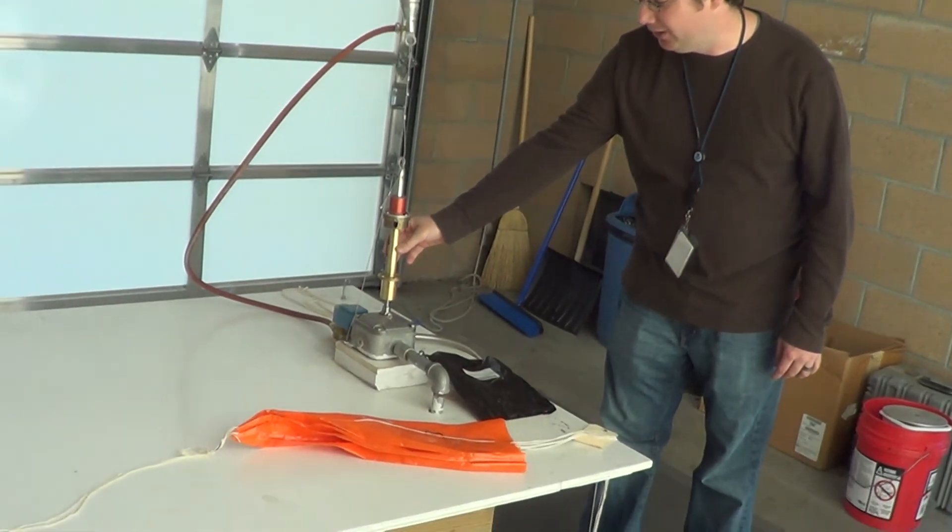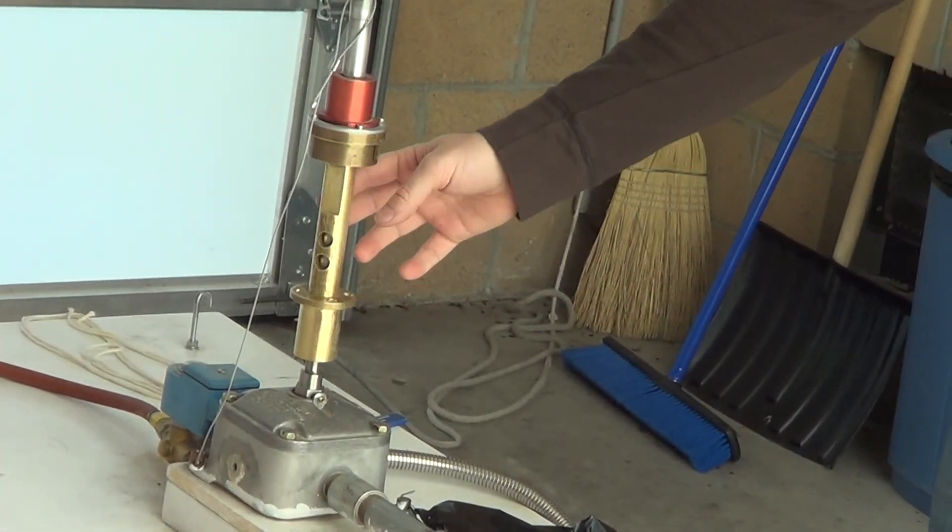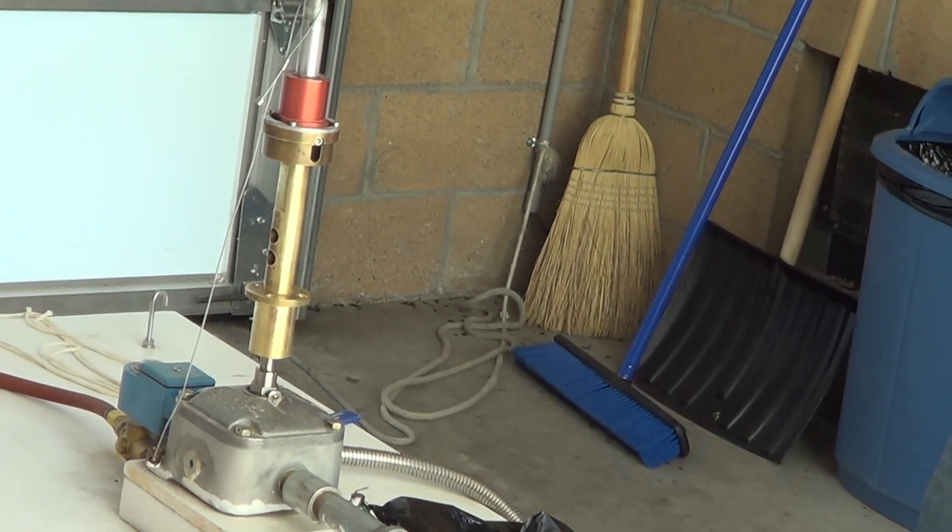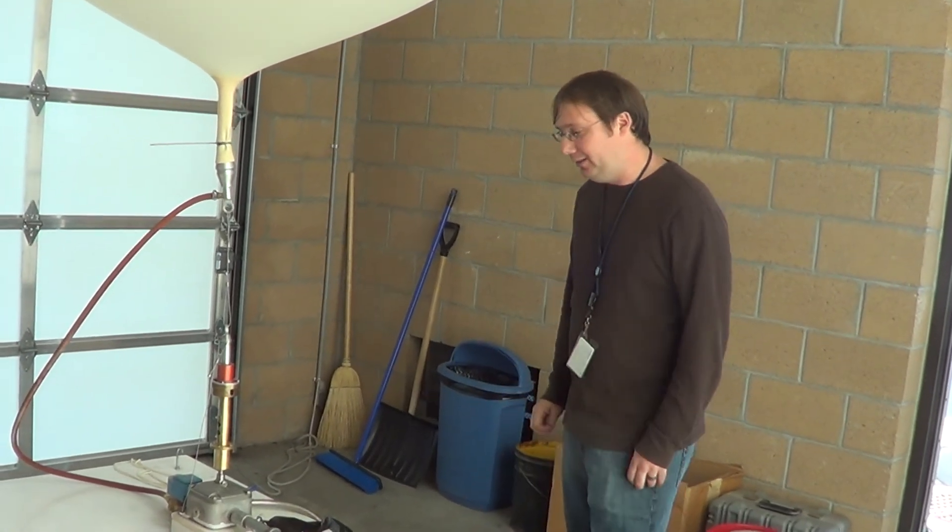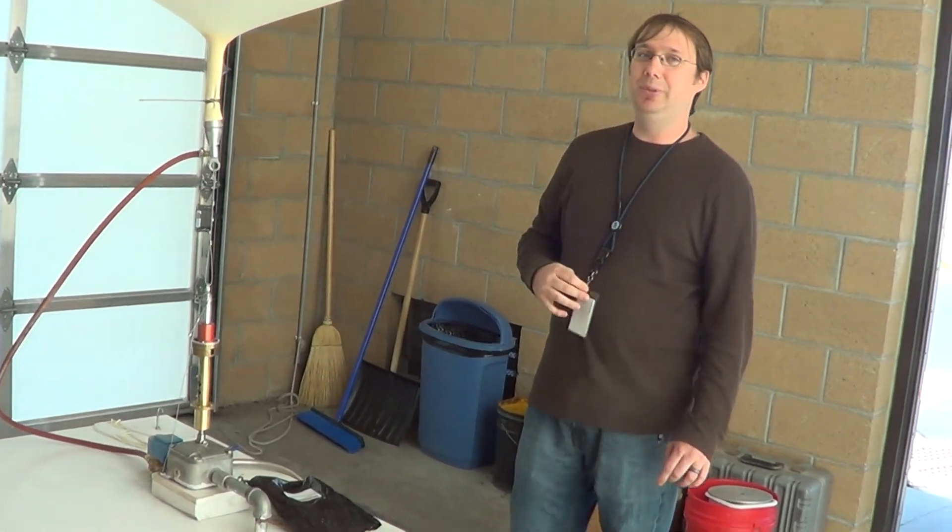And another little safety feature here is we do have brass fittings on everything from the hydrogen tanks linked to this little safety device that, if the balloon were to pop as we're filling it up, it'll cause it to shut everything down. And we do have fire extinguishers around.